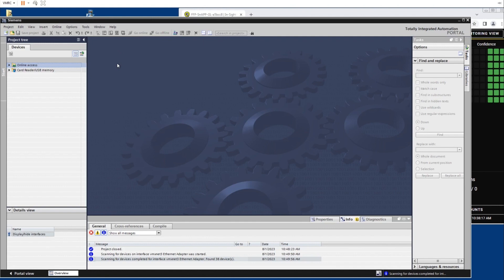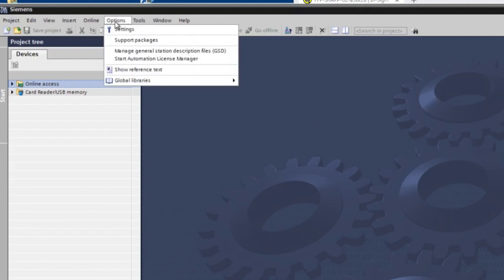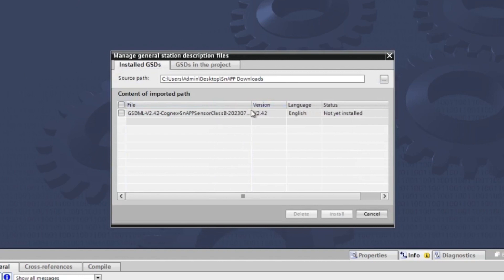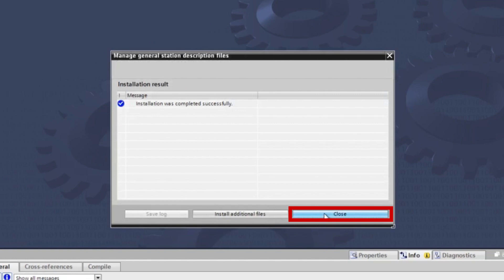To install the GSD file with a brand new program file, open the options tab and select manage general station description, GSD files from the list. A new window opens displaying the downloaded GSD file. Check the box next to the file and click the install button. Once installed, click the close button.